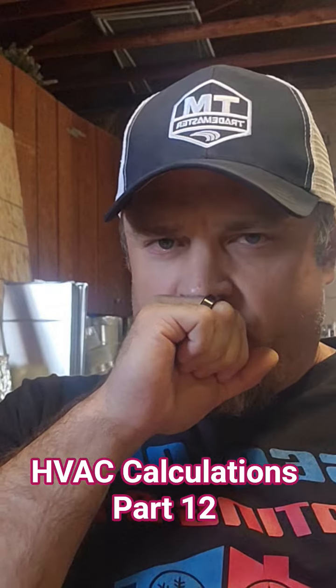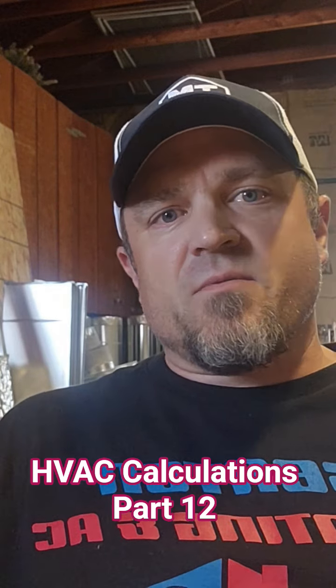So I implore any residential retrofit sales or layout guy to look at the ductwork first. If you notice the ductwork's undersized, tell the customer. If they don't want to spend any money on the duct, then you are not going to put a system in there that the duct can't handle. You're just not going to do it, because you're going to hurt the customer.